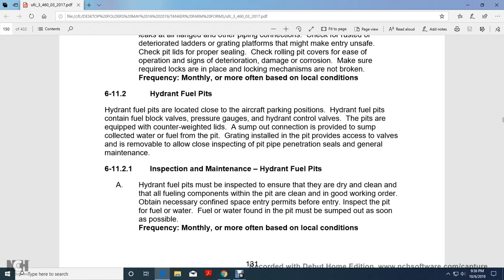The grating installed in the pit provides access for the valve, the removal of all closed inspection of the pit piping, penetration seals, and general maintenance. Inspection and maintenance of hydrant fuel pits: hydrant fuel pits must be inspected to ensure that they are dry and clean, with all the fuel components of the pit in good working order.